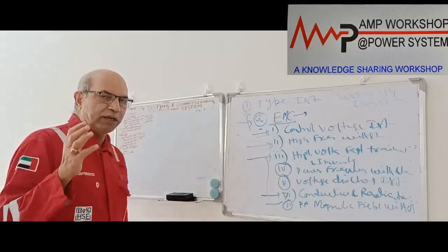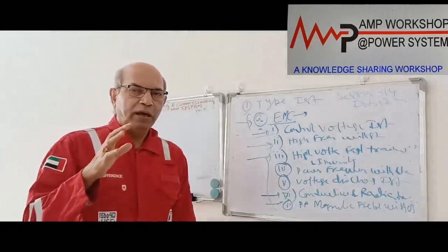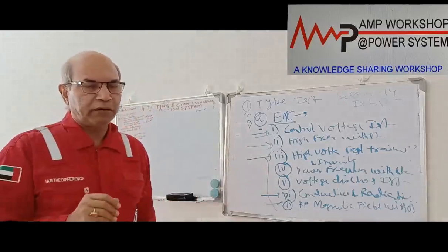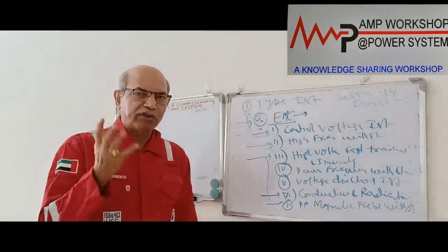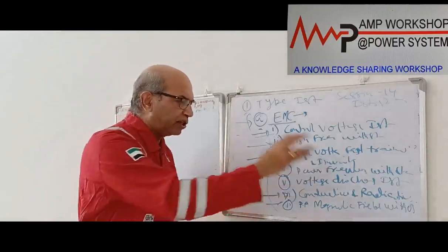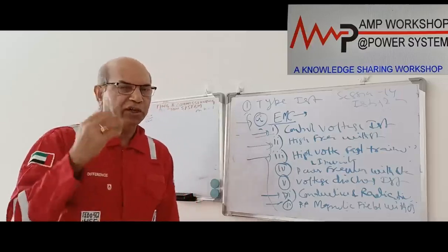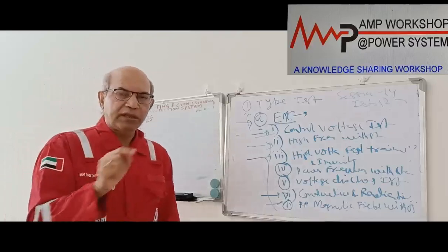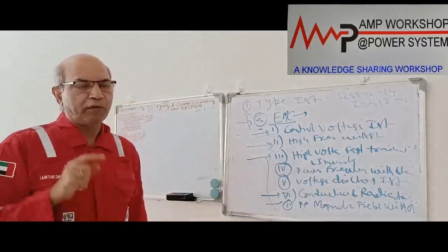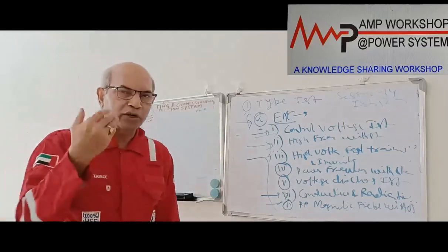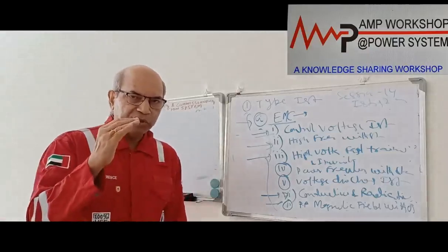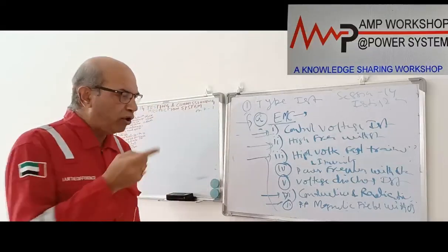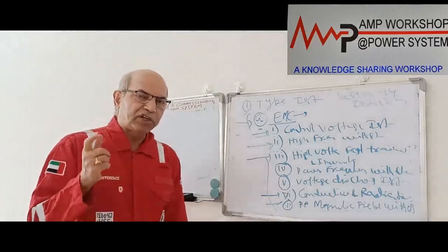Now you know any relay may have a cover, maybe an insulated metallic cover, and this cover will get electrostatic charge. It is actually the electrostatic discharge test. If somebody touches it, immediately a spark over will occur, and when the spark over occurs a high voltage will be generated, and this high voltage sometimes causes maloperation of the relay. That's why we need to do the electrostatic discharge test.